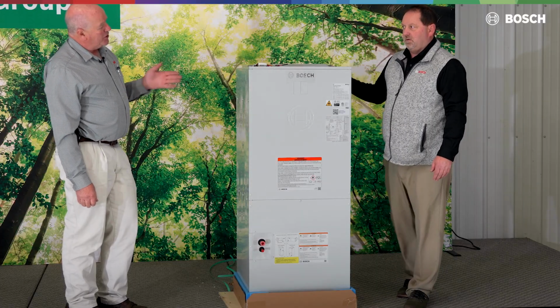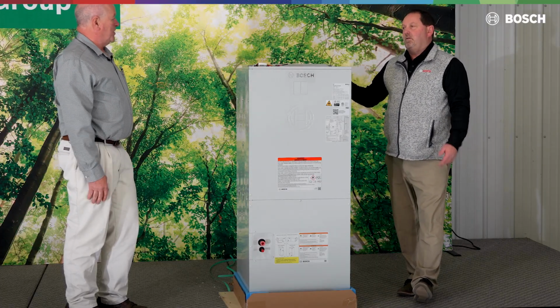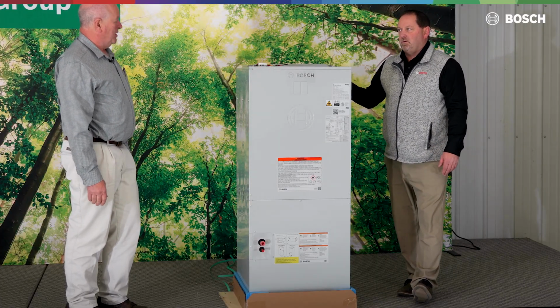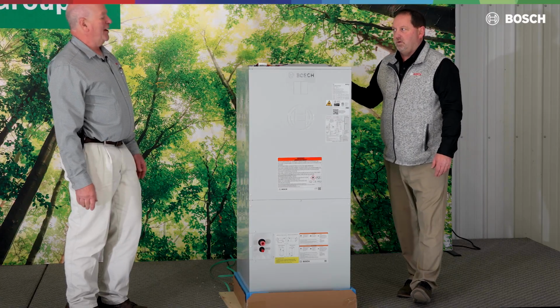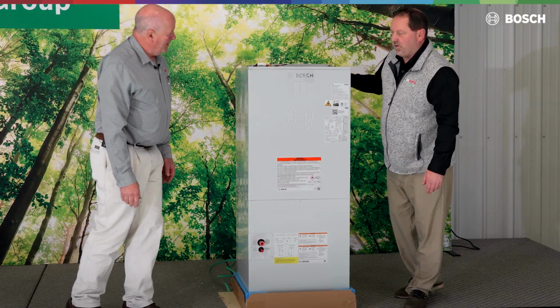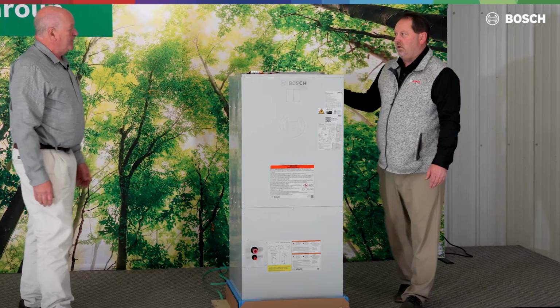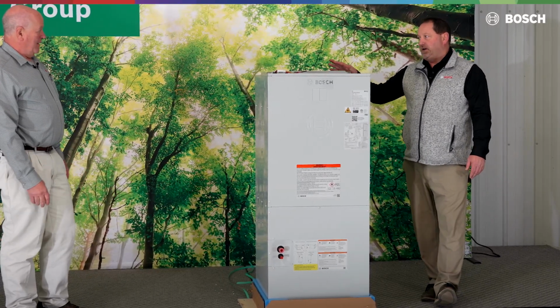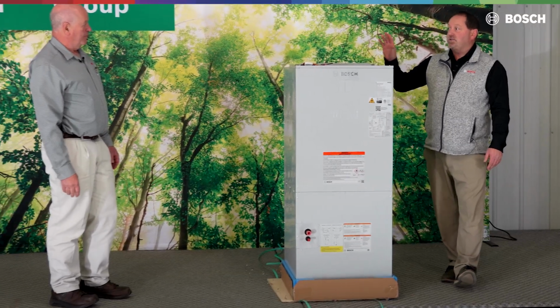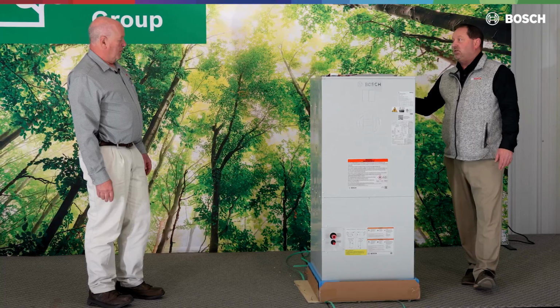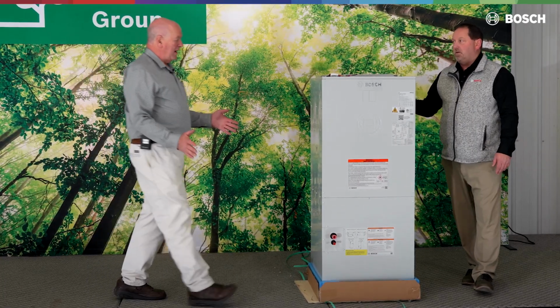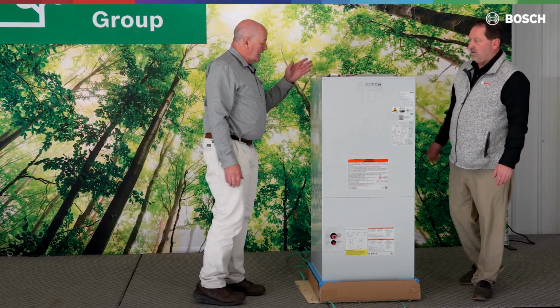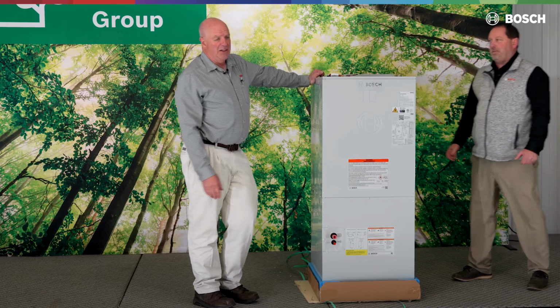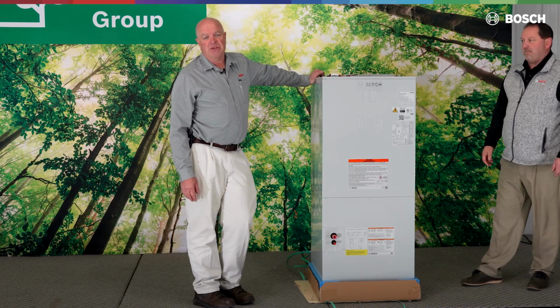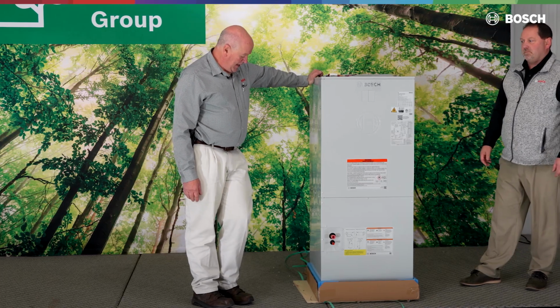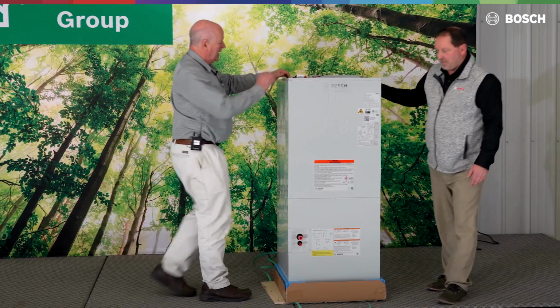We just don't want to match up the unit we took out for sure and say it's going to be the same, because sometimes those units will be miscalculated from the beginning. So what size is our outdoor unit? Our outdoor unit in this case is a 5-ton. So you mentioned load calculation. Right. So we're going to size the unit to the load of the house. We're correct. Okay. We do the heat loss, Manual J. In this application, we have a 1600 CFM duct delivery system, so that's why we chose to go with 1600 CFM. So to get this off the rest of the way, Chris, I'll pick up my side.